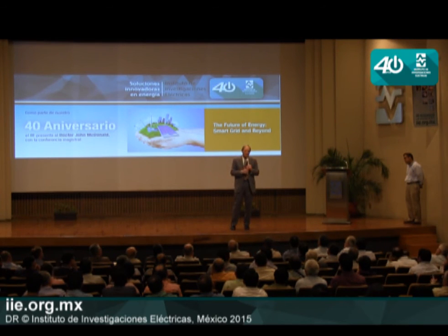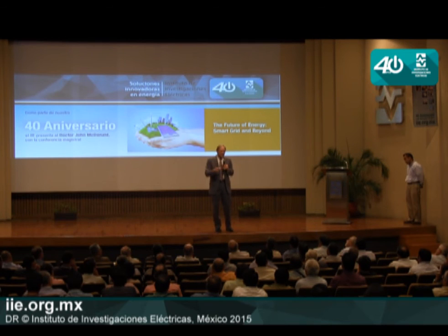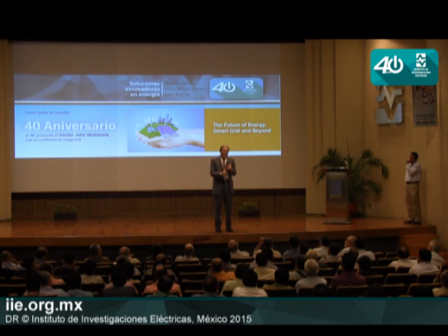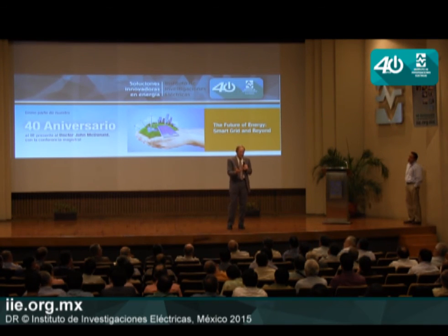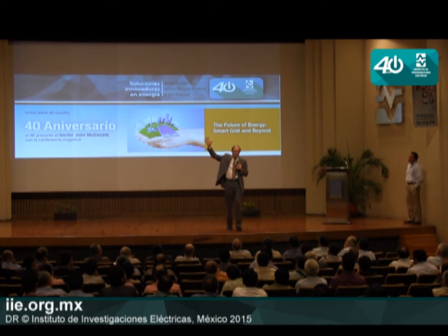That's an important point. Third lesson was the value of testing. We thought we tested adequately in the factory, then went out in the field. What we forgot was that these integrated solutions go from substation to the control center or office, and we didn't do enough end-to-end testing. You can test the meter and its communications and it works fine, but out in the field the meter communicates with the head-end system, the network management system that manages metering communications, and it wouldn't work. We didn't test that in the factory.